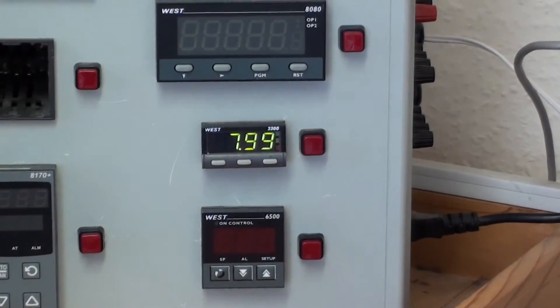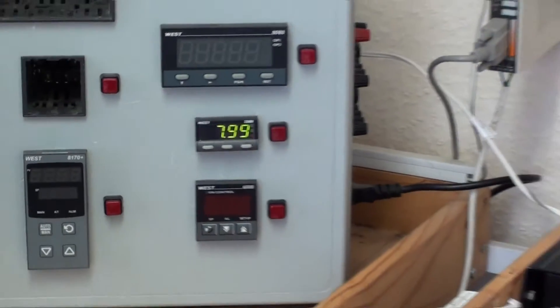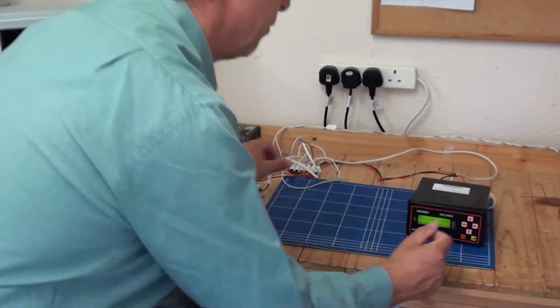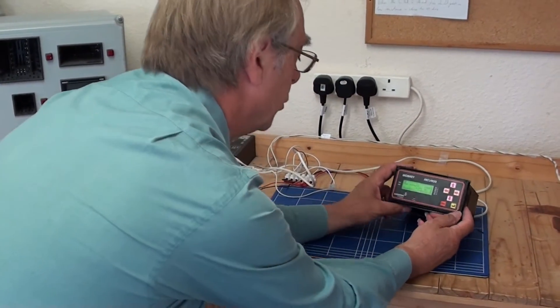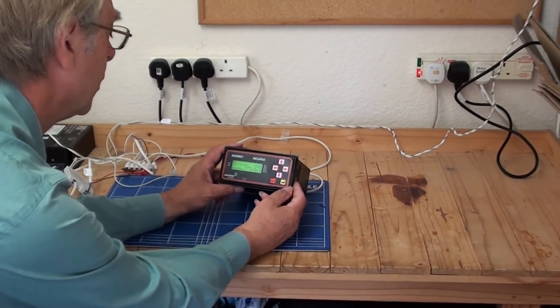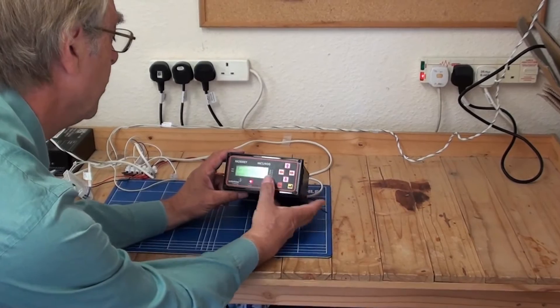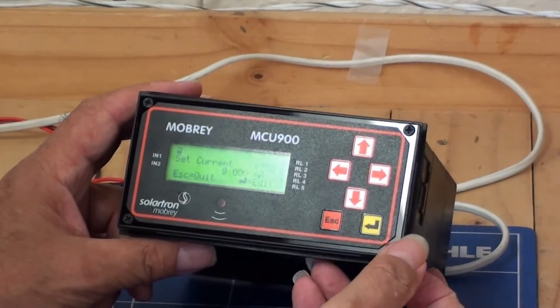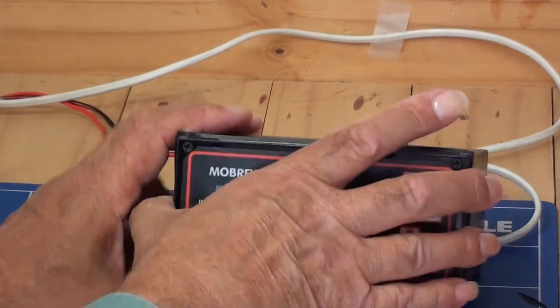With the control unit giving the 4-20mA signal to the SEM1200, there is a commissioning tool where I can set the current. If I go into that and set, say, 12mA, we should see the same on the two indicators.